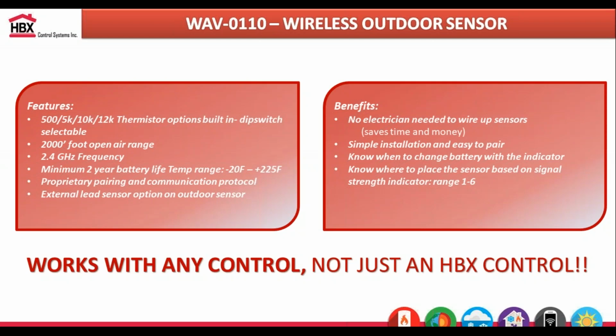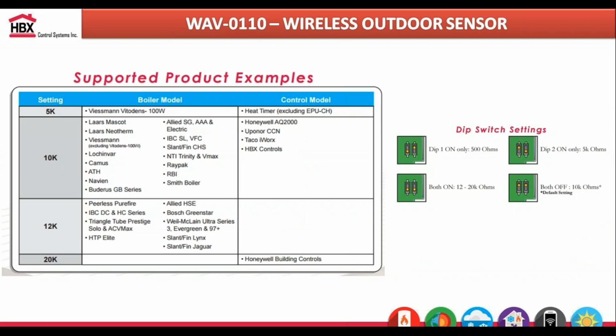There are built-in DIP switches on the controller itself. Most boilers will run off a 10K or 12K curve, so we try to give you as many boiler manufacturers as possible in the manual. Like I said, most of them run off the 10 or 12K. By default, it runs off the 10K ohm. If your boiler needs the 12K, you just flick the DIP switch either up or down.